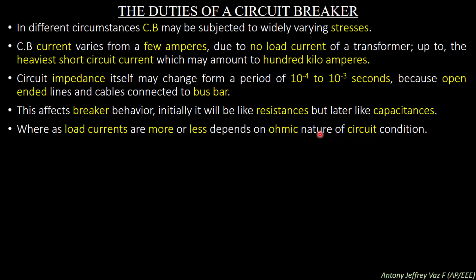Whereas load currents depend more or less on the ohmic nature of the circuit conditions. We know the long transmission lines are made of copper, and these copper lines will have I square R loss. So these I square R losses represent the ohmic nature of the material. The transmission lines running for a long distance will also be inductive in nature, and this inductance will create an inductive short circuit current when the lines are unloaded. We know all the transformers, generators, transmission lines and everything we are using are made up of coils. So this inductance creates a short circuit current which is also inductive in nature, whereas only unloaded lines are capacitive in nature.